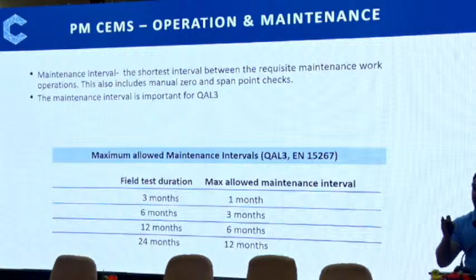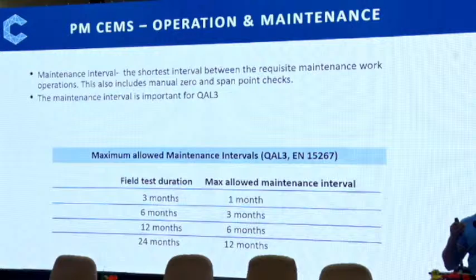When the certification is done, it also comes with a manual saying that this particular equipment requires calibration after a certain interval. If you see in the table, for the field test done with that equipment for 3 months, the maximum allowed maintenance interval is 1 month. If you look at the bottom one, the field test done for 24 months, for a longer time, the confidence is more, and it says you can do the maintenance calibration at an interval of 12 months. But it is not written on the wall. It depends upon how you do the operation, how clean your operation is, how well you maintain it.